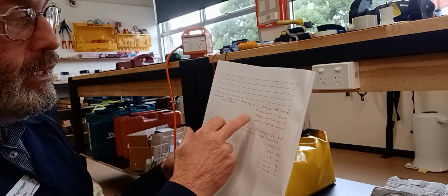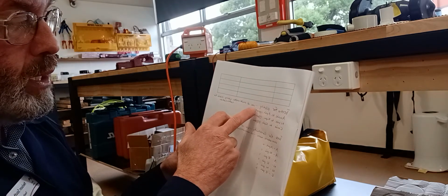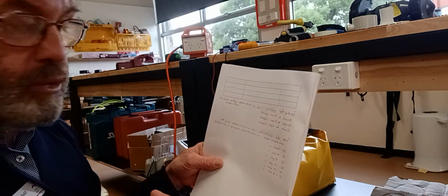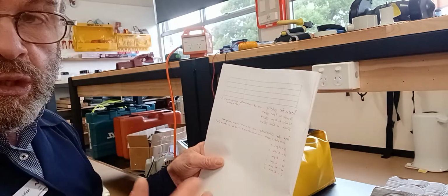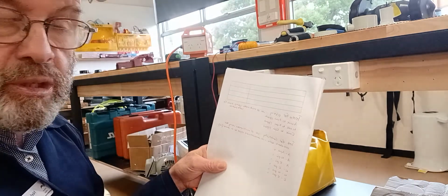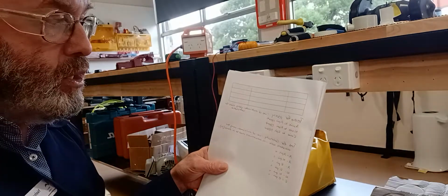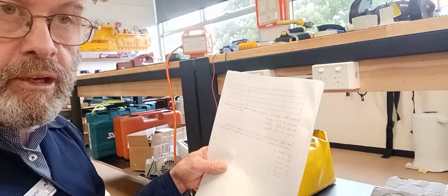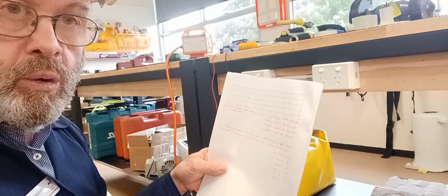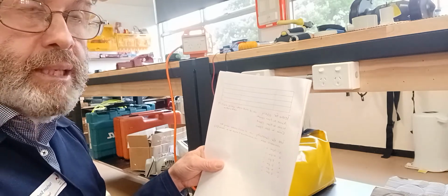While we're doing each of those tests 1, 2, and 3, while you've got one of the wires of your multimeter on the active, test the neutral and earth pin, and there should be no noise. Test the function of the switch of the power point as well. In the off position, you should get no noise when you're going active to active, but when you turn the switch on, you should become a closed circuit, and that proves the function of the switch.